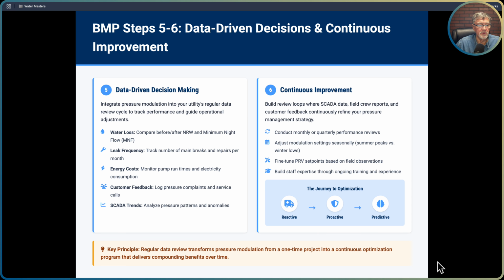Energy costs, you're going to want to monitor those, as well as customer feedback, any pressure complaints and service calls. Sometimes we can take this customer feedback and these complaints and tie them back to specific pressure zones in our systems or even specific valves. And now we can nail things down. But to do that, you have to integrate your data back and forth and not have data silos, where you've got a little bit of customer data over here and operational data over there, and they're not talking together. You can use customer complaint data to actually influence your operations and get at the core of some of the problems. So that's important.